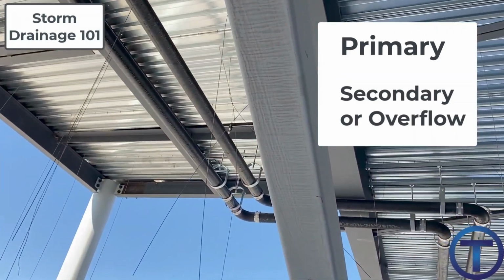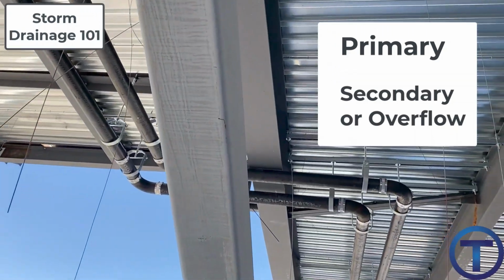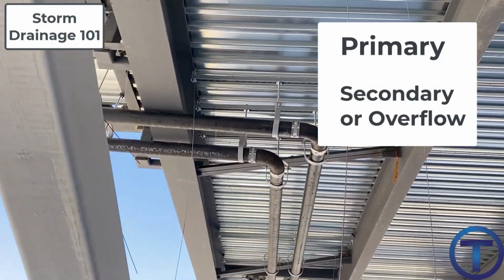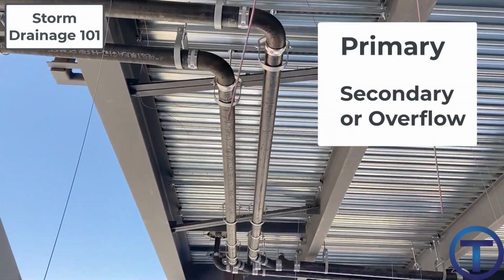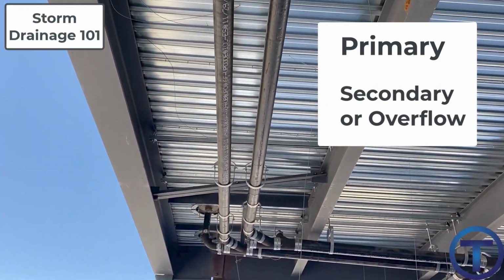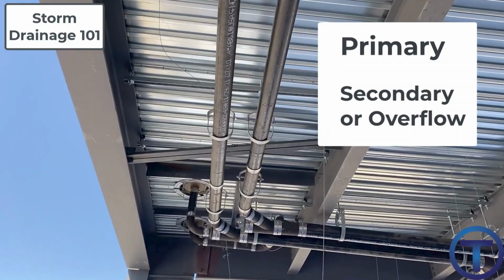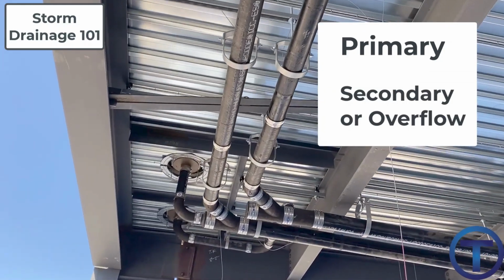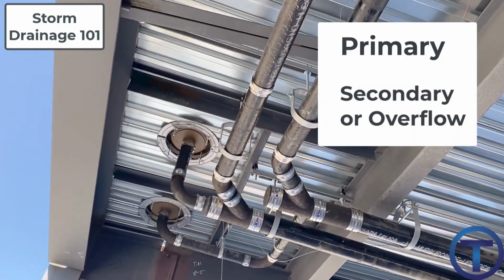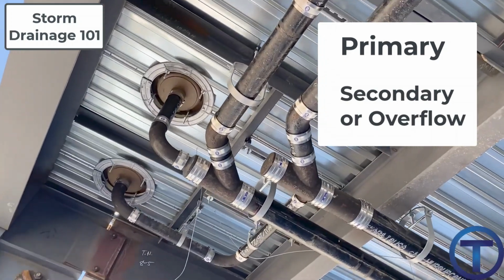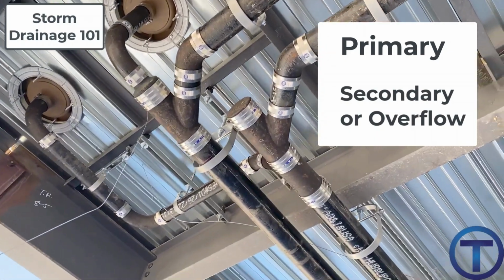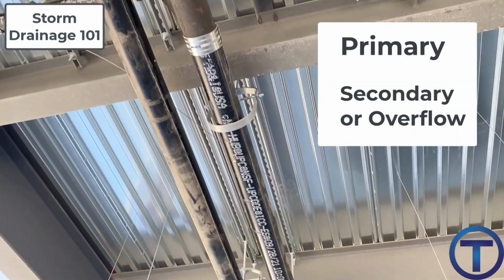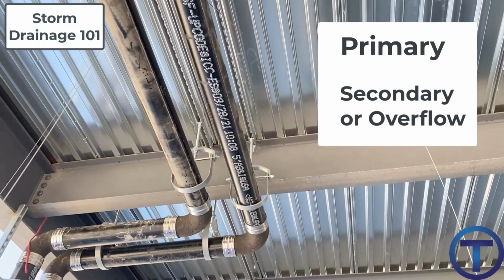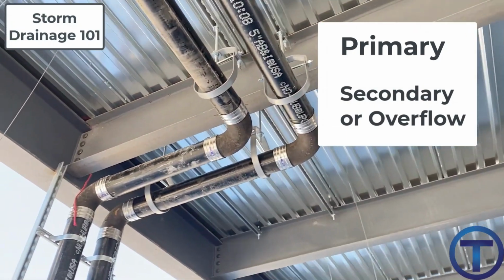Say we have a 100-year storm and it dumps like crazy. It has to be able to hold that much water. But the secondary drain or overflow roof drain is installed and designed, again, the exact same diameter as the primary drain, but its purpose is to convey the water off of the roof if the primary drain gets plugged up. So this way we have a backup, and that's all that it is for.